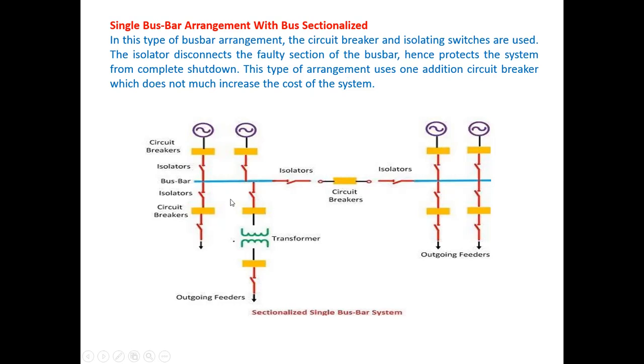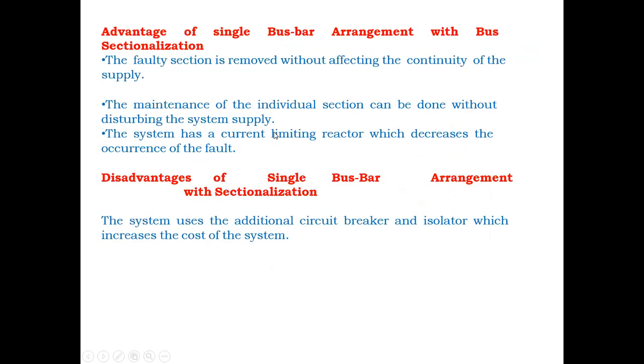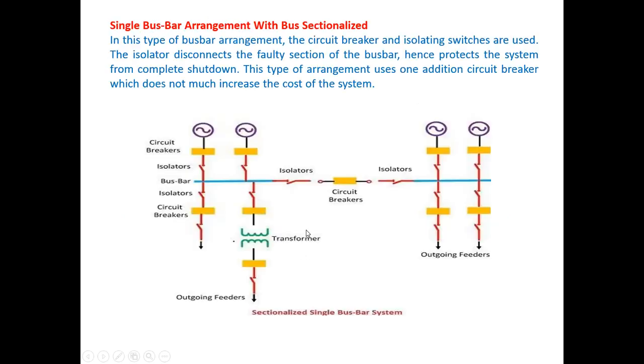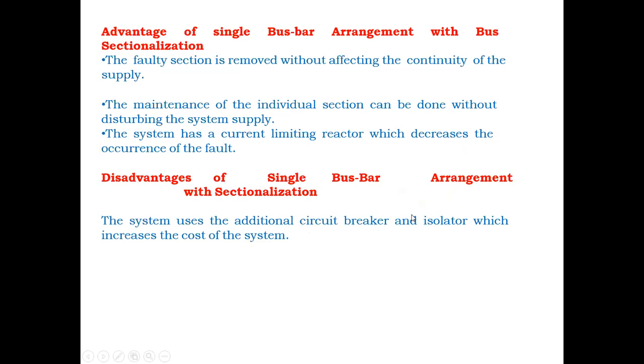Under emergency conditions, we can open the isolator and perform maintenance of the bus bar. The advantage of single bus bar with sectionalizing switches is that the faulty section is removed without affecting the continuity of supply. The disadvantages are that additional circuit breakers and additional sectionalizing switches are required, which increases the cost.